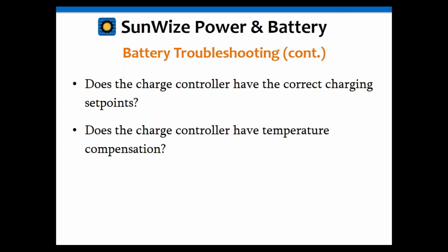As I mentioned, correct charge controller settings and temperature compensation. Actually, I was just helping a customer again recently. They had the charge controller in a sealed box with other electronics, and the battery was in a separate box that was vented to ambient temperature. They were using a charge controller that had temperature compensation, but it was inside a sealed box and not near the battery. They had to add a remote temp sensor to it.